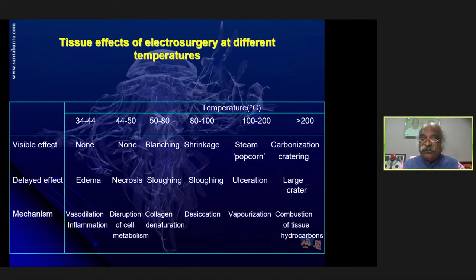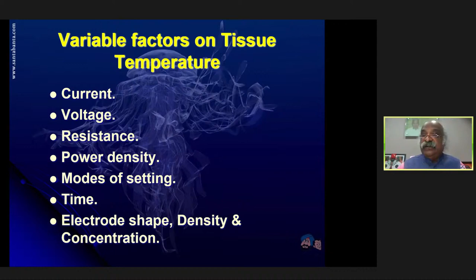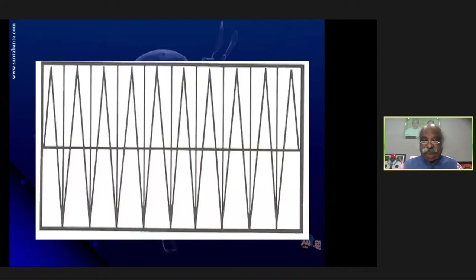Now, apart from this, there are variable factors affecting tissue temperature. What are the factors that affect the tissue temperature? Number one is the current. If the current is more, the tissue temperature will change. Voltage, then resistance, which is the capacity of impedance. Power density, the mode settings of the electrosurgical generator, and timing: if you touch slowly and for a long time, there are different effects. And the electrode also: the design of the electrode, the shape, the density and concentration of current at the tip also change the tissue temperature.